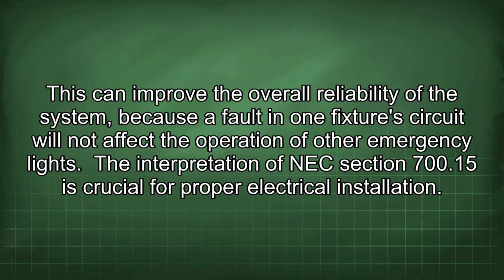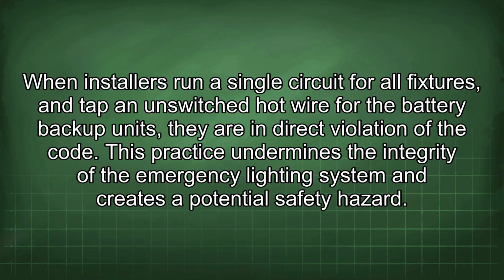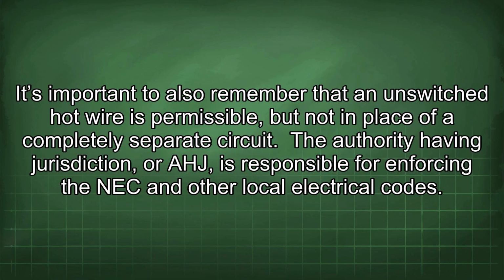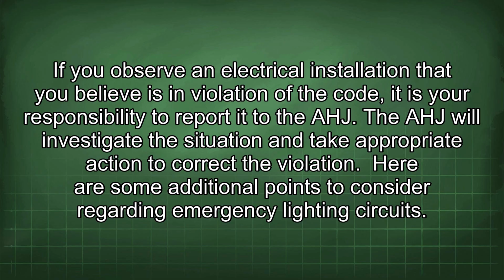The interpretation of NEC Section 700.15 is crucial for proper electrical installation. When installers run a single circuit for all fixtures and tap an unswitched hot wire for the battery backup units, they are in direct violation of the code. This practice undermines the integrity of the emergency lighting system and creates a potential safety hazard. It's important to also remember that an unswitched hot wire is permissible, but not in place of a completely separate circuit. The authority having jurisdiction, or AHJ, is responsible for enforcing the NEC and other local electrical codes. If you observe an electrical installation that you believe is in violation of the code, it is your responsibility to report it to the AHJ. The AHJ will investigate the situation and take appropriate action to correct the violation.